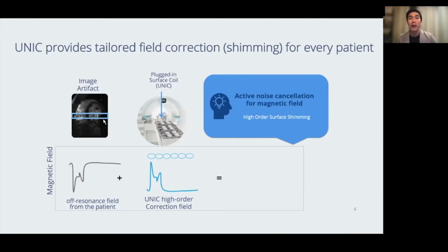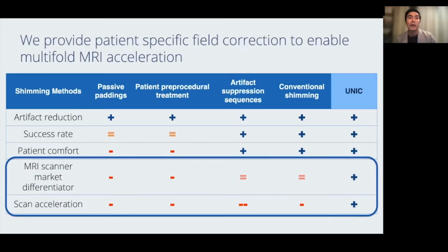Similar to the popular active noise cancellation headphone, we first measure the shape of the disrupted magnetic field. And utilizing the high-order shimming capability of our coil, we can generate an identical cancellation field to cancel out the interference. By combining these fields, we are able to eliminate the noise and generate high-quality images without artifacts. Because of the precise shimming capability, our coil provides a high success rate without compromising patient comfort.